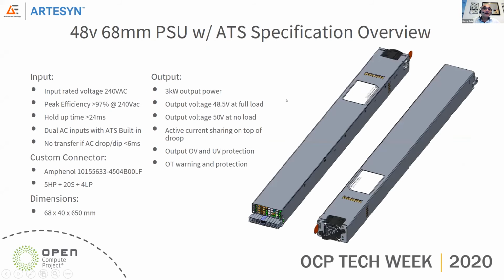Diving into the PSU specifications, the power supply has been optimized for 240 volts operation. It has a very challenging 97% peak efficiency, which is a great number considering that the power supply has an ATS embedded in it. As pointed out by Ming and Carsten, it has a very high hold-up time, upwards of 24 milliseconds. The PSU has built-in dual AC inputs with ATS. The output is 48.5 volts at full load, and 50 volts at no load, with the usual protection circuitry.